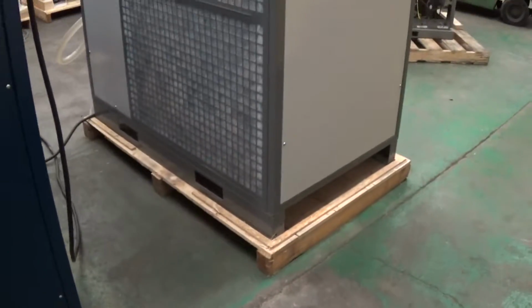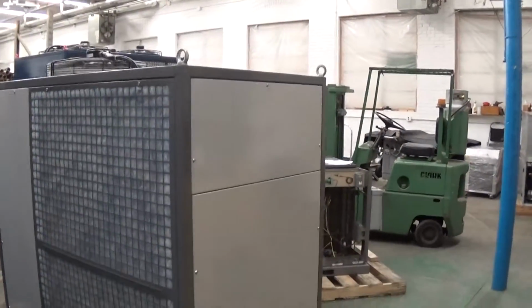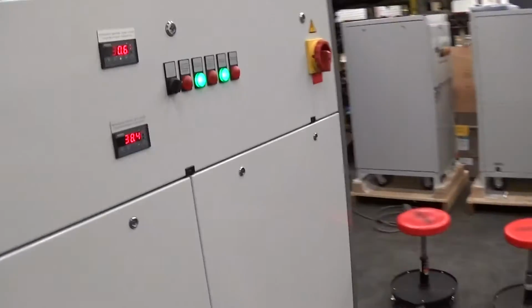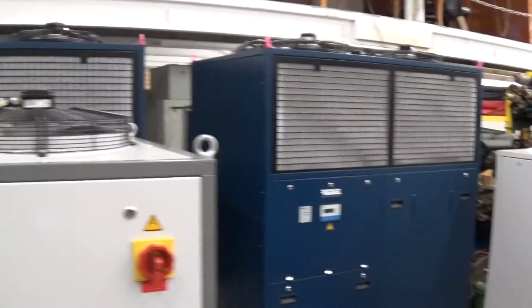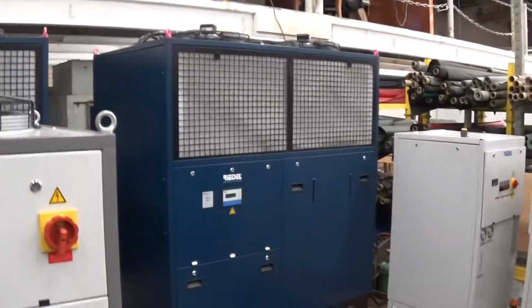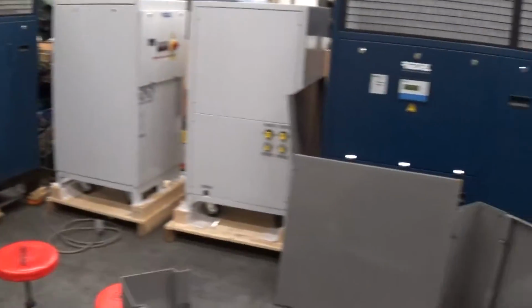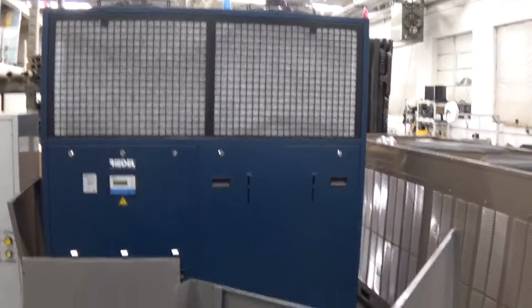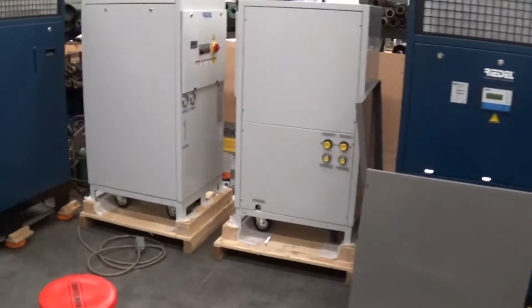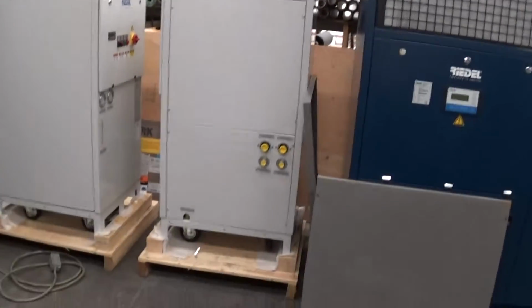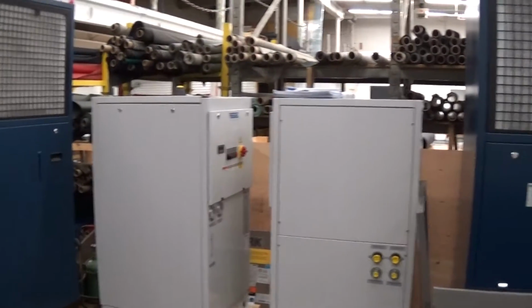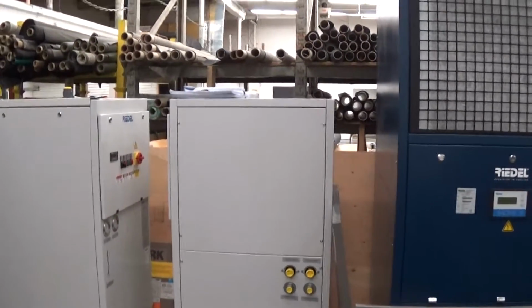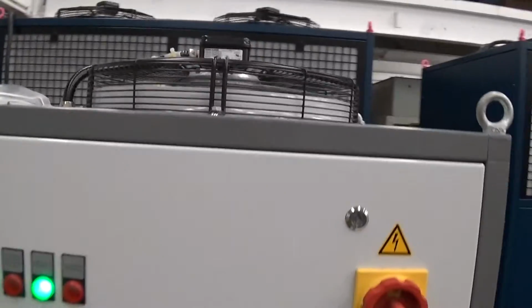We've tested lots and lots and lots of chillers. The Riedels are nicely engineered equipment. We have these 3 blue ones here, these 22-ton units. Those sold a long time ago and paid for. The customer is just waiting for some type of permitting process for their plant. Then we have these 2 here. These are water-cooled units. That requires either cooling tower water or a secondary water source, so they don't have the fans that you see up here.